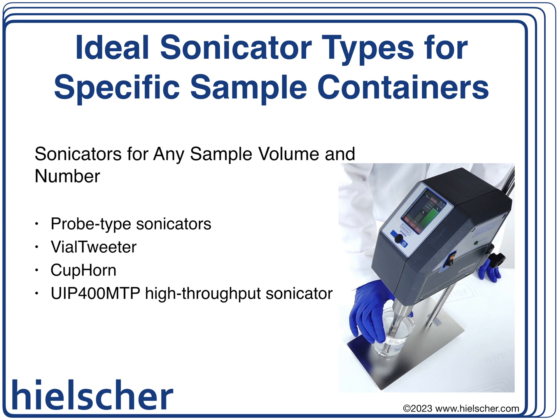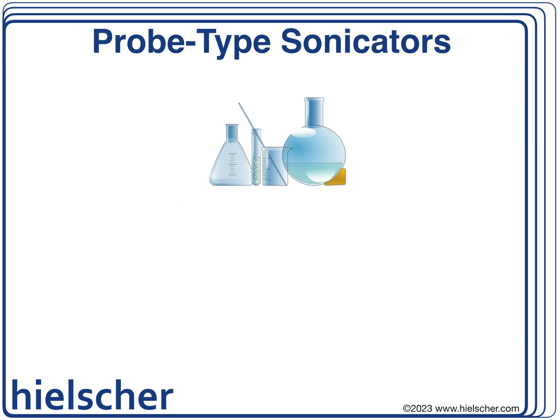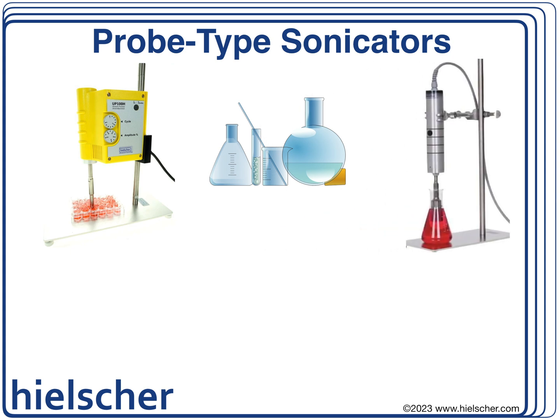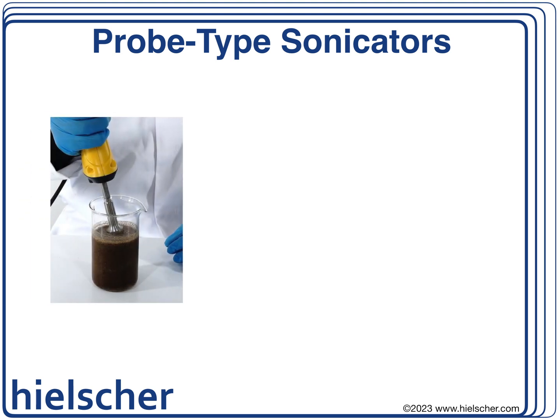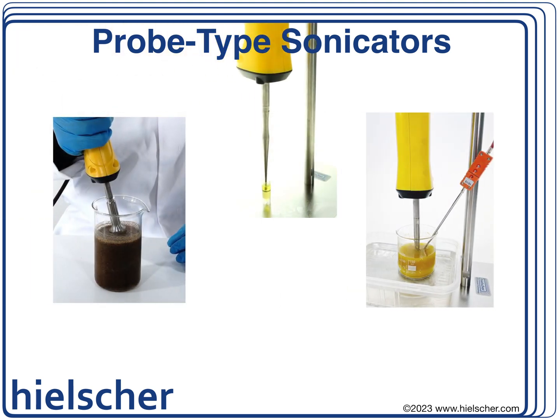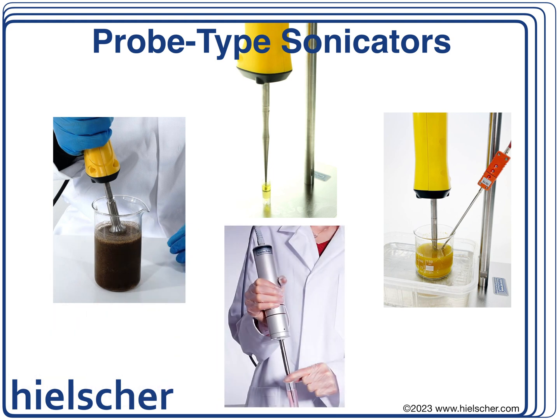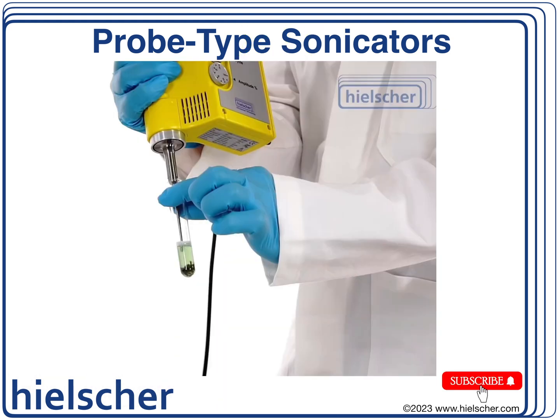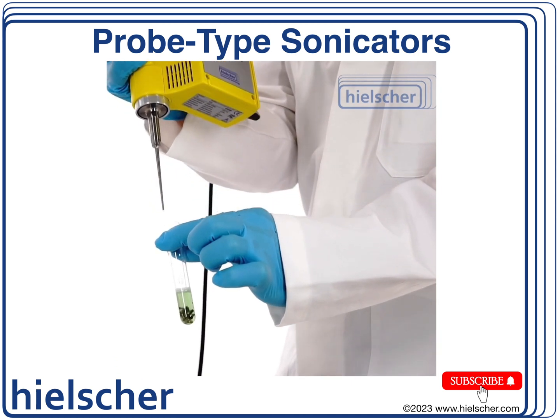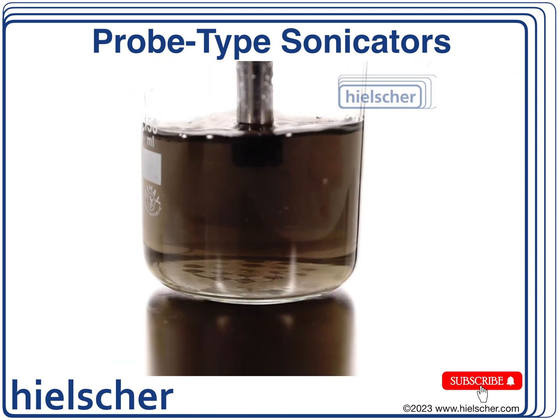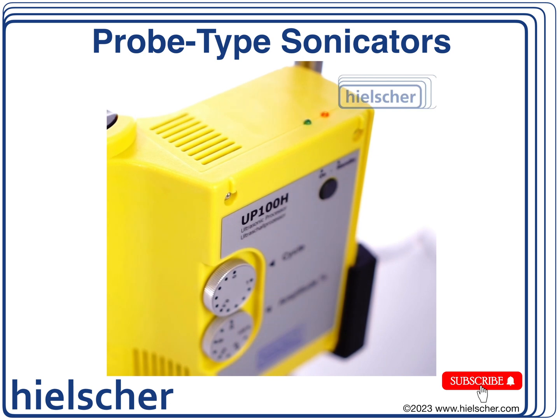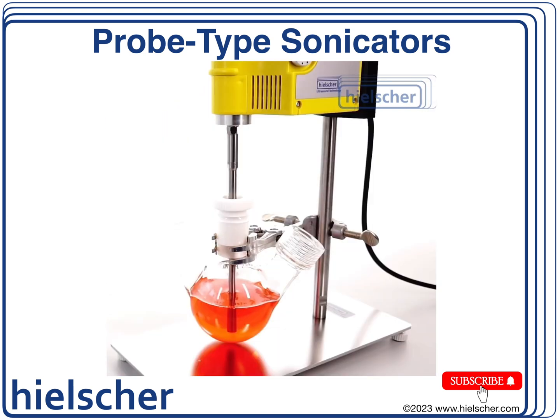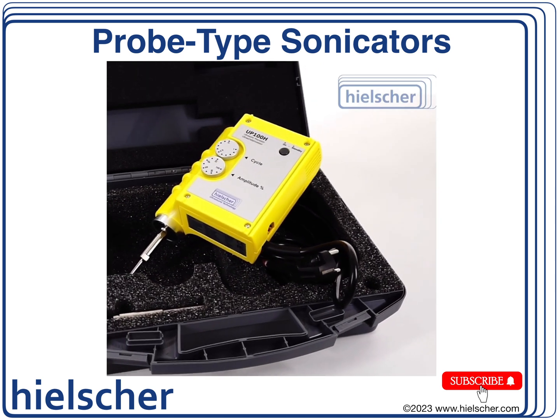Now let's explore suitable sonicator models for each container type. The probe-type sonicator is a popular tissue homogenizer found in many biological and biochemical labs, used for cell disruption, protein extraction, cell solubilization, DNA/RNA fragmentation, and buffer solution homogenization. Probe-type ultrasonicators excel for large sample volumes and smaller quantities — the tip or sonotrode is inserted directly into the sample, exposing the liquid to ultrasound waves. With different sonotrode sizes and shapes, they are adaptable for beakers, flasks, vials, and tubes.